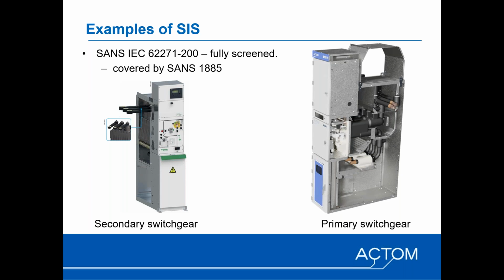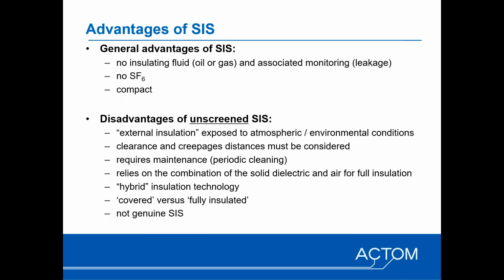And then you've got the fully screened type, which also of course falls under -200 with a metal enclosure, covered also by SANS 1885. And on the left is the Schneider Premset, secondary, although the ratings are increasing now up to 1250 amp 25 kA, but fundamentally a 630 amp switching device. And then on the right is the Actom GelPag solid dielectric insulated switchgear solution, which we'll talk about in detail later on. So what are some of the general advantages of SIS?